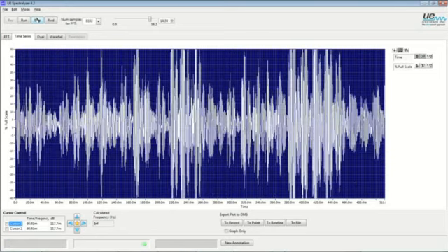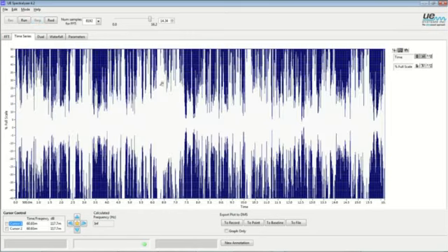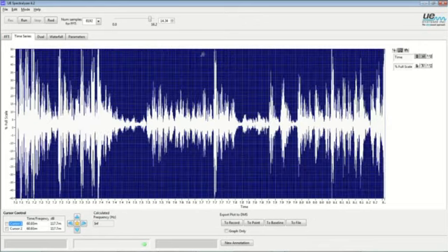And even stopping the recording here, it really visualizes how the changes in amplitude, or the intensity of the discharges, are taking place throughout the recording. And looking at the entire 16 seconds, it shows the periods even better with the peaks and valleys. From the timing aspect, as we zoom in on this, that becomes even clearer how non-uniform the discharges are occurring. There's no pattern to when in time we can expect the discharge.